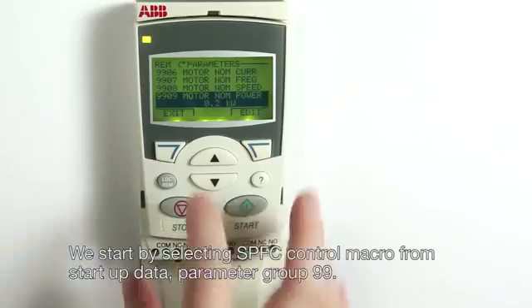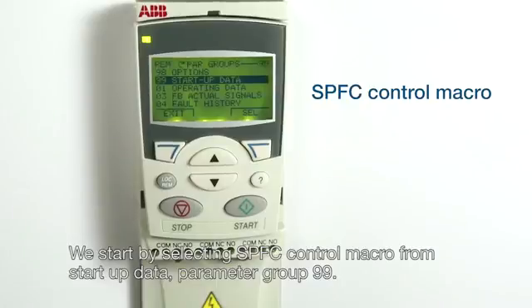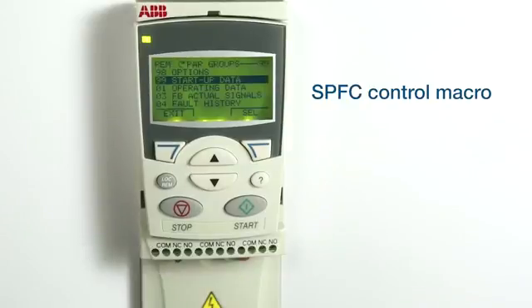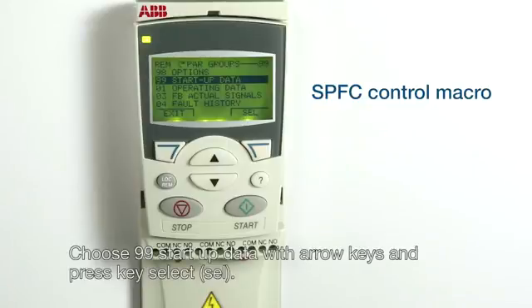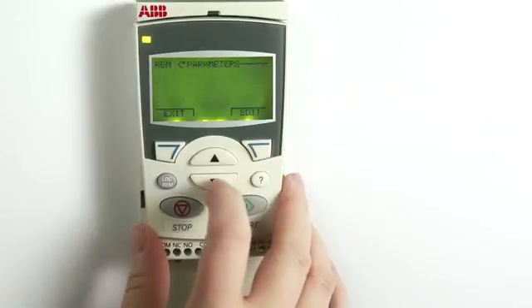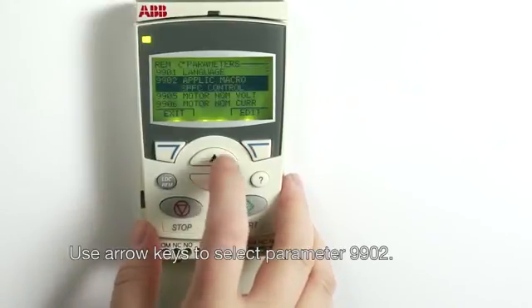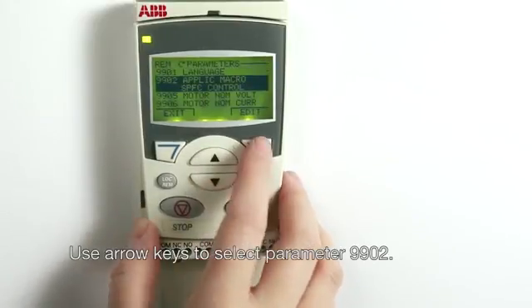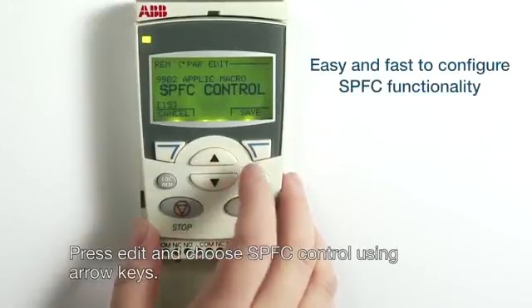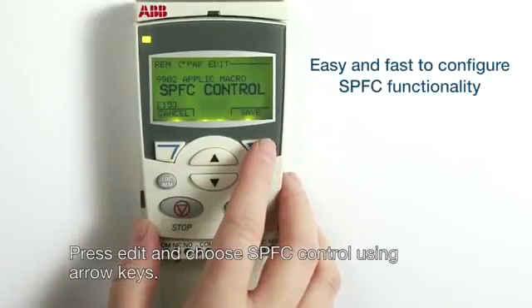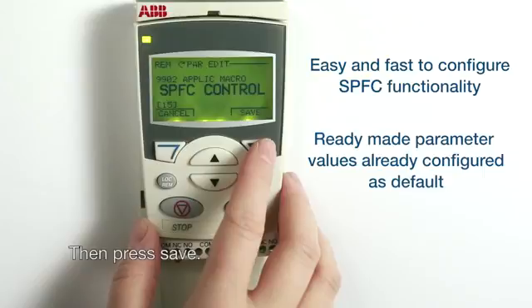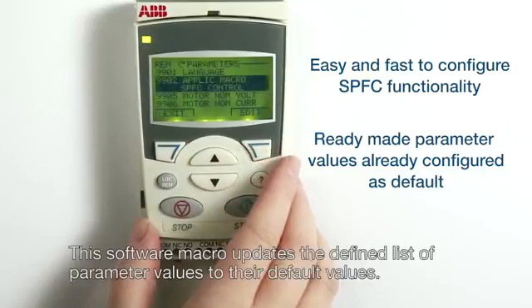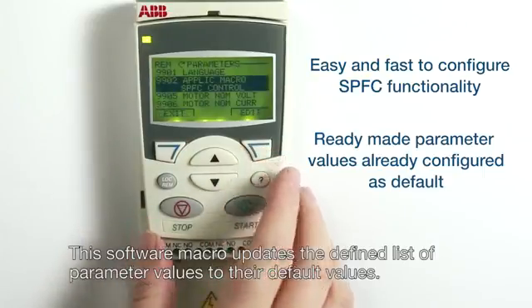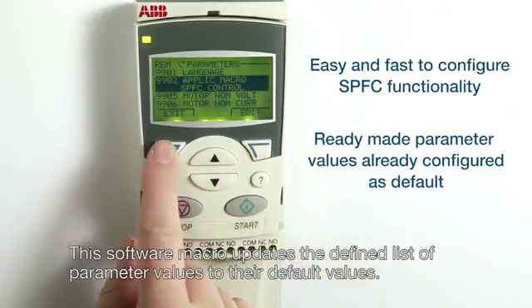We start by selecting SPFC Control Macro from Startup Data, parameter group 99. Choose 99 Startup Data with arrow keys and press Select. Use arrow keys to select parameter 9902. Press Edit and choose SPFC Control using arrow keys. Then press Save. This software macro updates the defined list of parameter values to their default values.